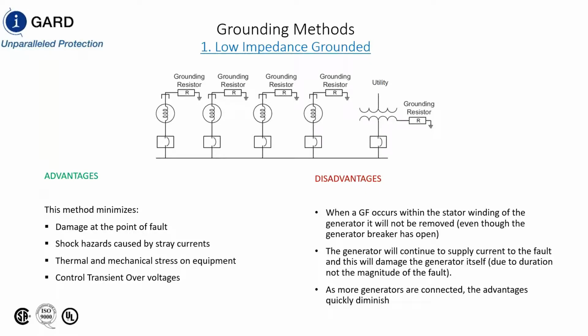That is a lot of current, and you're going to cause a lot of damage in your system, specifically if it's in the stator winding. You have shock hazard and stray currents, you have thermal and mechanical stresses, and transient overvoltages. The disadvantages: if a ground fault occurs within the stator winding, that generator is out for repair, and it's out for a long time, and that's what happened in the Pacific Northwest. The generator that had the damage was out for such a long time.